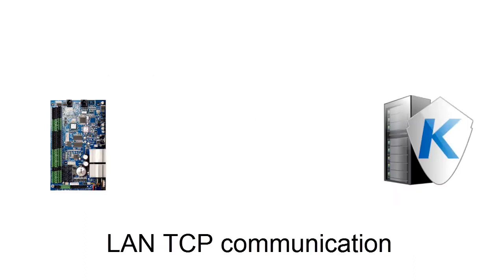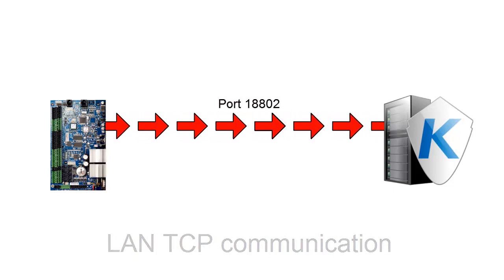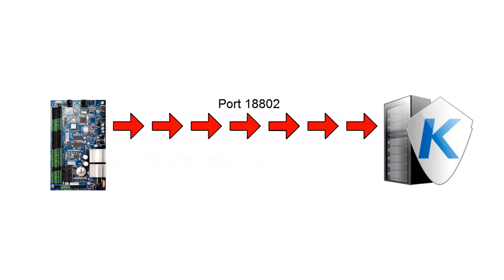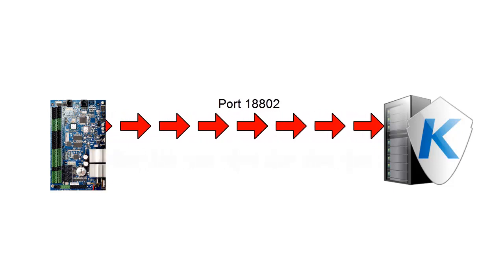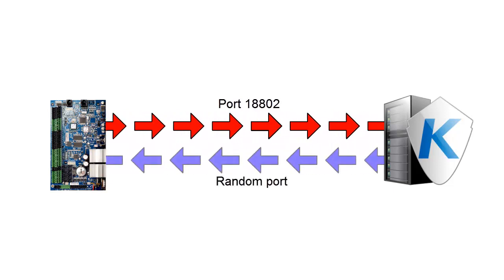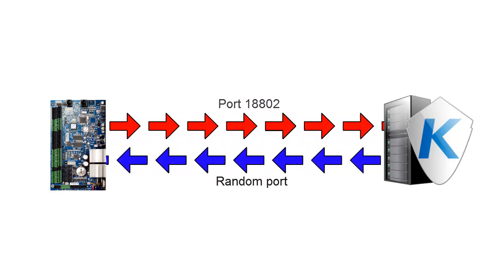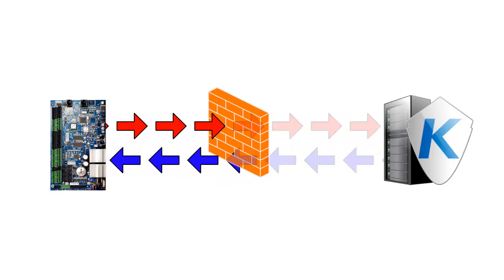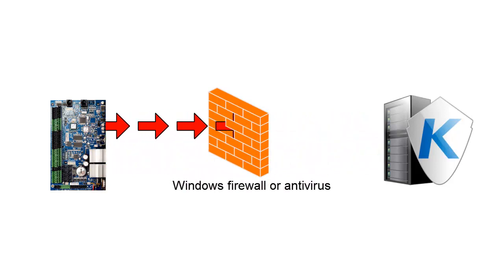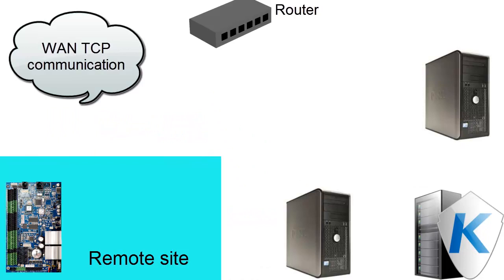The controller will initiate communication with the software. It will send a request on port 18802 and await for an answer on a random port. This communication, of course, can be blocked by a firewall or an antivirus.